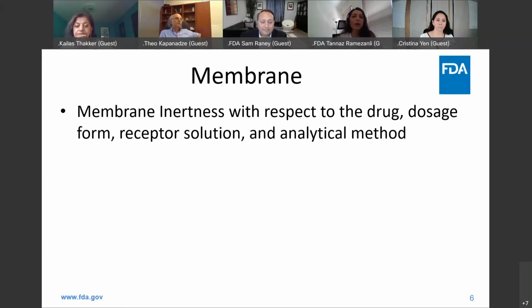Okay, thank you. Can I just add something to that? Sure. I was just going back to most of the ANDAs I've looked at. Most of the time, like Sam said, we accept the membrane binding data. Most applicants also take it a step further and describe the physical nature of the membrane after the study. So that can give us an idea whether the membrane was the right one that was chosen.